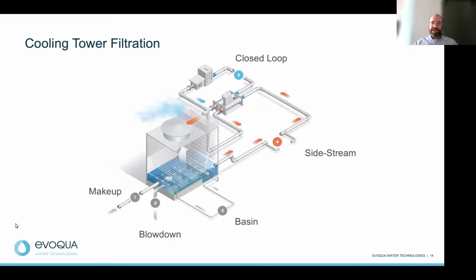And then lastly, number 5, don't forget about closed loops. Although they're closed loops, we often know that there could be leaks. So there's a lot of makeup water, especially if you have a makeup meter, you can see how much it's losing per day. There can be construction projects. And although that is a closed loop, a lot of those have high oxygen contents. And so that can really increase the corrosion rates of the mild steel. So again, depending on your specific situation, these products that Mike is going to run through can really help you in a variety of ways in both your open and closed loop.